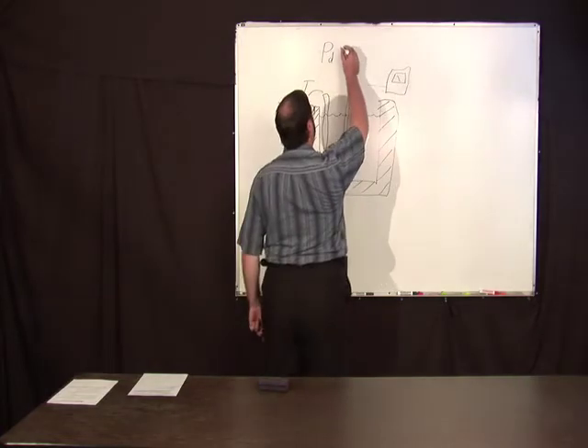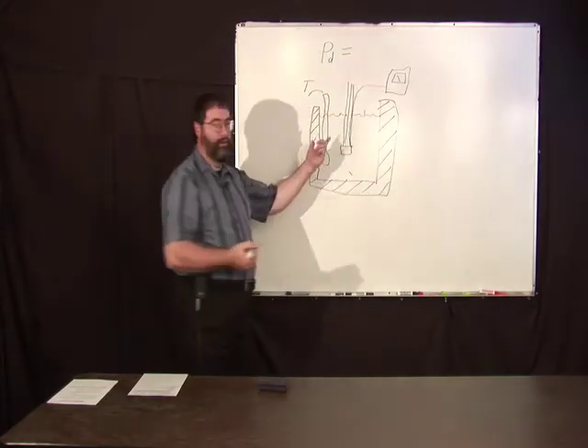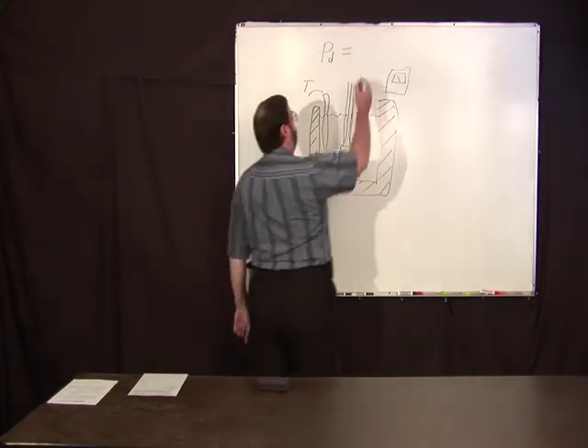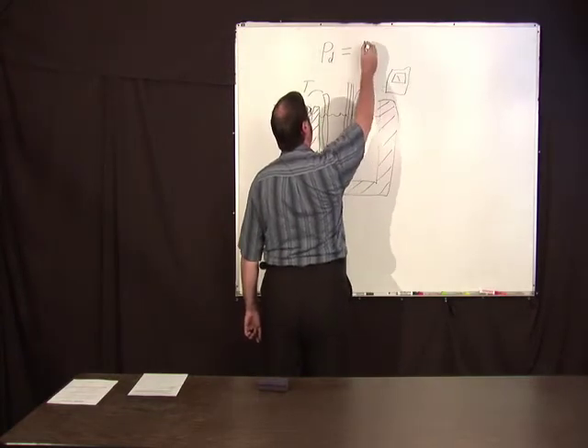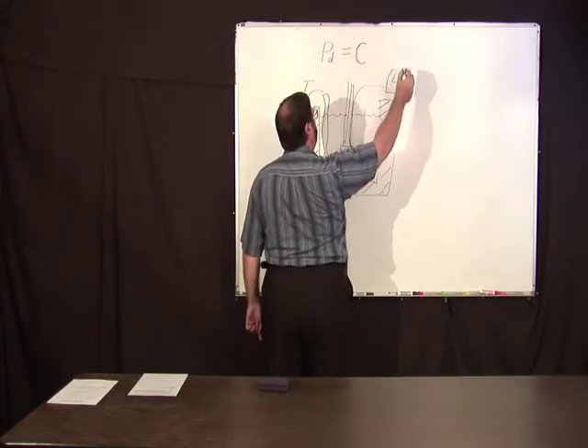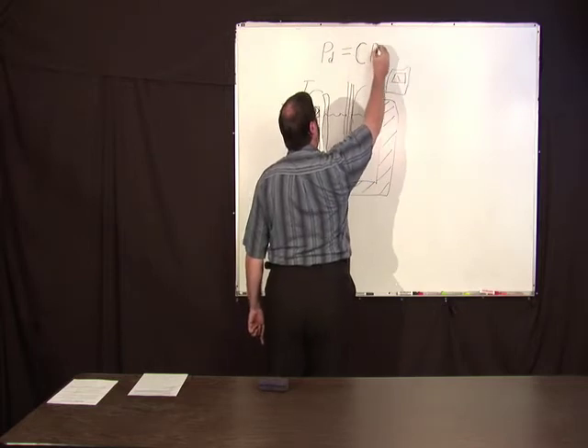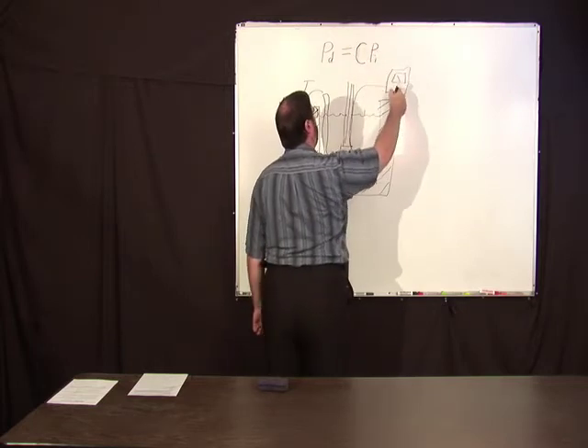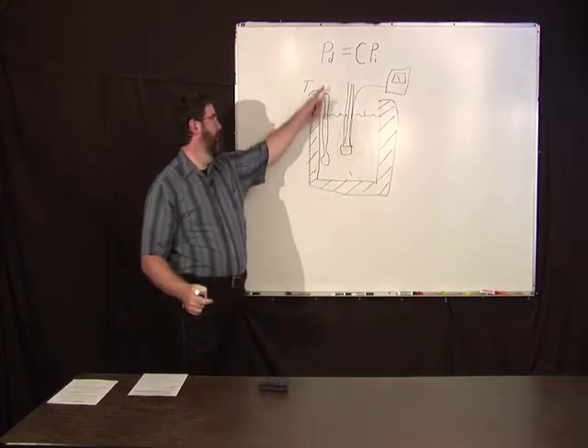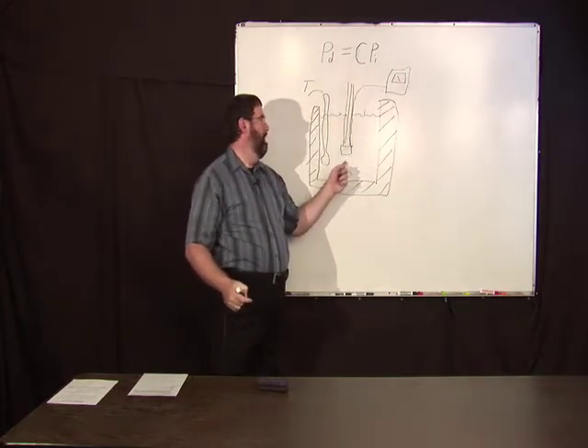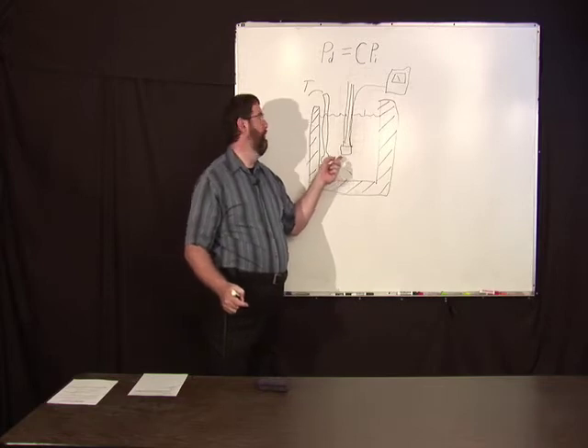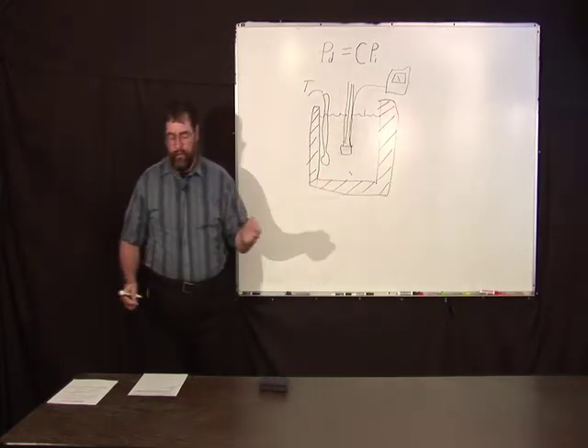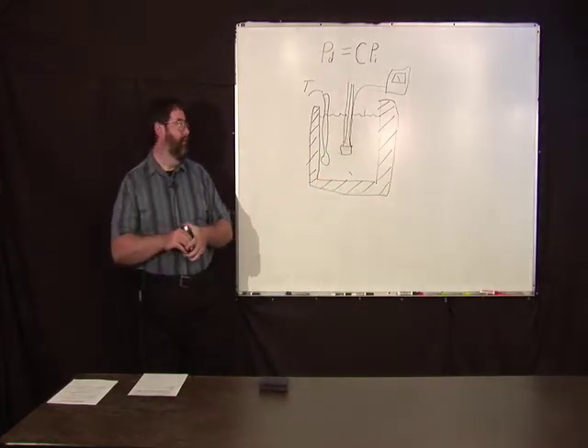What we're talking about here is called calorimetry. Let's say you have some power delivered. You can precisely compare that to your resistor so you can figure out what the actual power delivered to this device is, in this case, an RF power sensor. By measuring temperature, it's going to be some constant - let's call it C - times the power indicated on the meter, because they're not going to be the same. That sort of calibrates the meter.